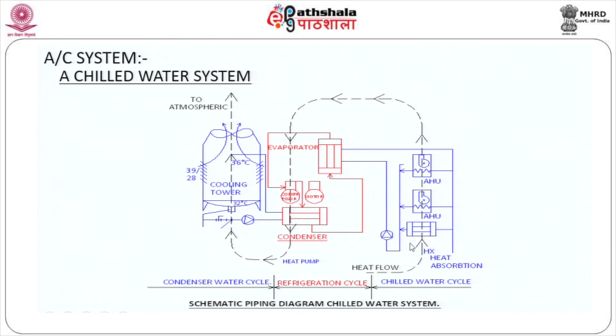Invariably in such large applications, it is a water cooled application. So the water cooled condenser needs cold water from a cooling tower, which is drawn by this pump and recirculated here. So this blue circuit is the heat rejection part, this blue circuit is the heat absorption part, and this is the magic item which moves heat from here to here. Now by doing this, you have cooling available to be used in, as I said, multiple zones.